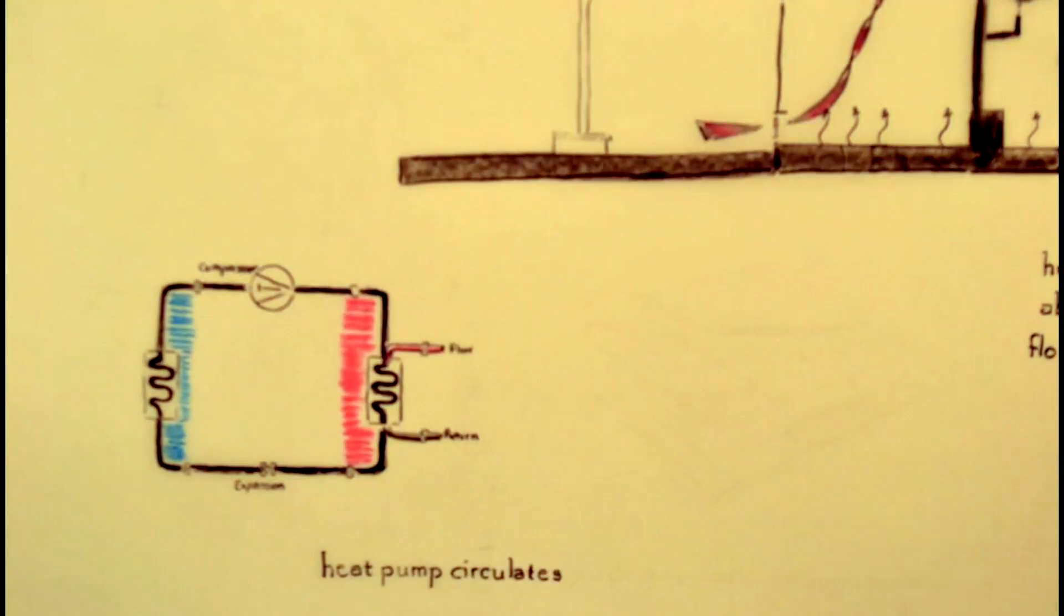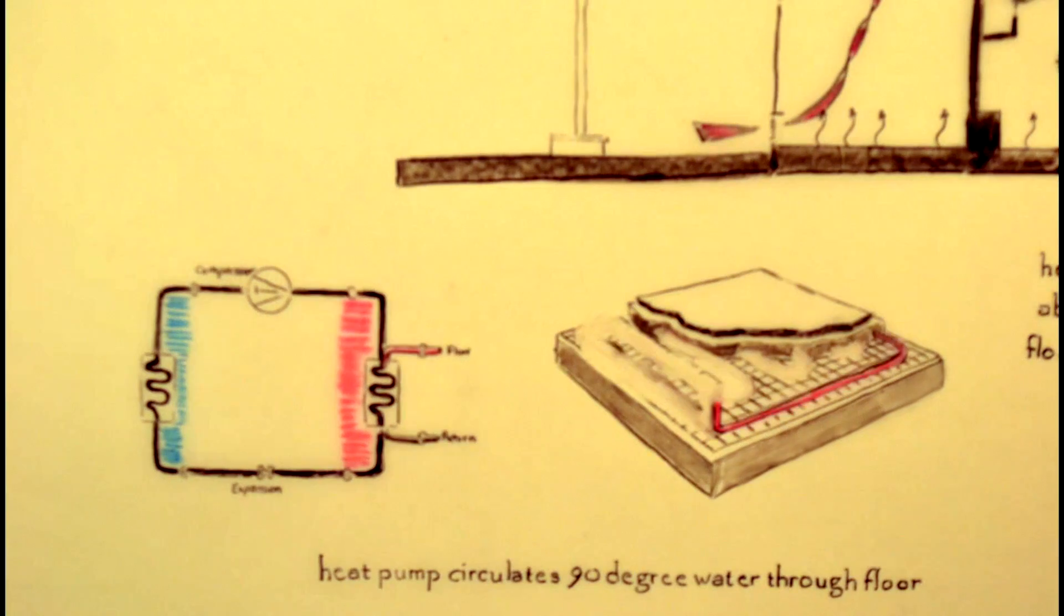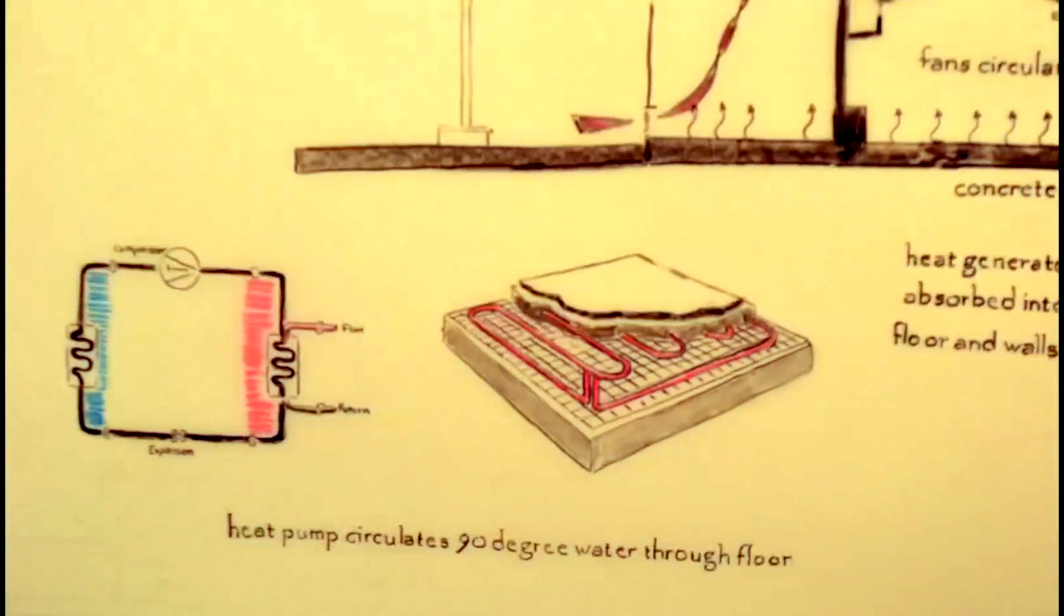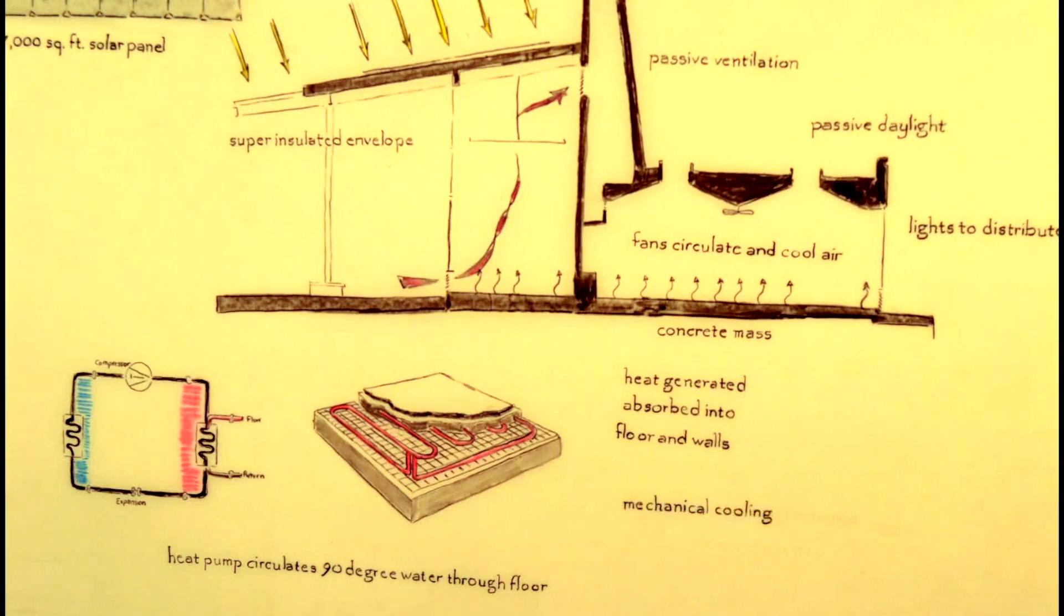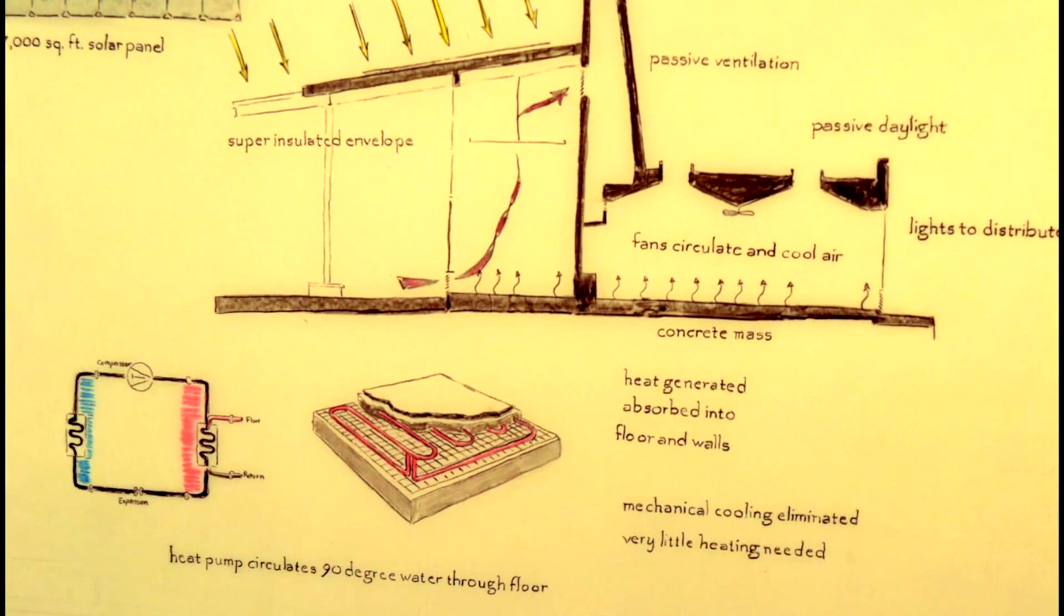The heat pump circulates water at 90 degrees Fahrenheit through pipes embedded in the exposed concrete slab. Under these combined systems, all mechanical cooling is eliminated and very little heating is needed.